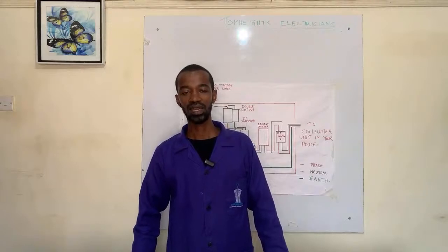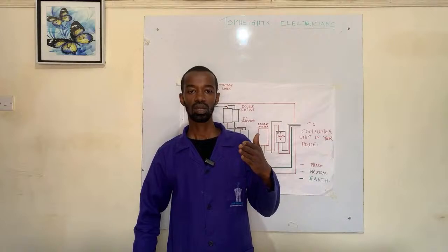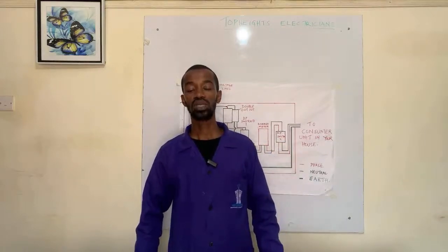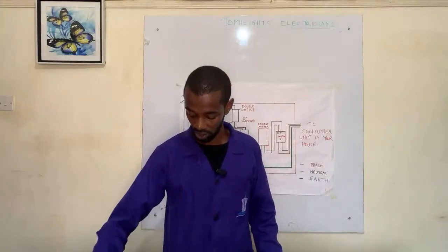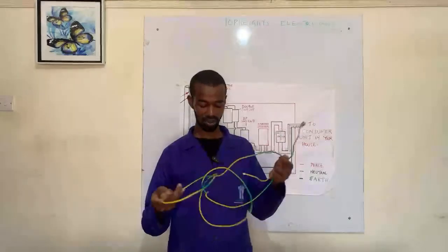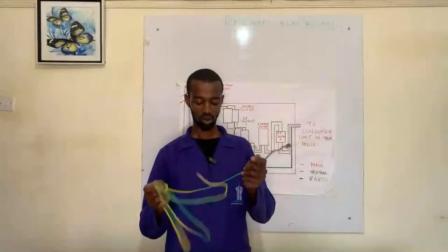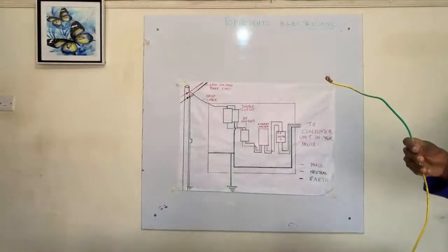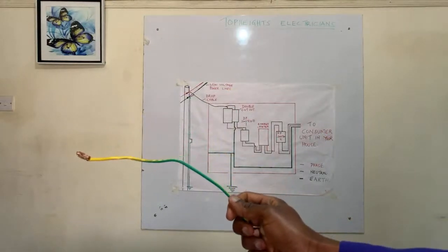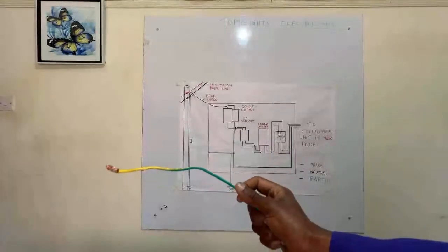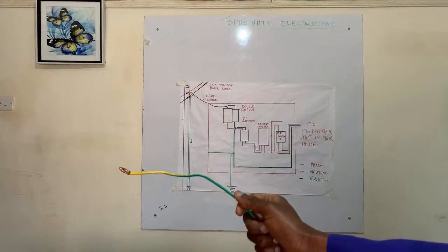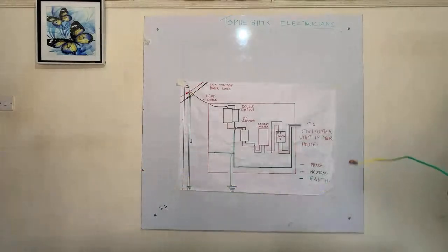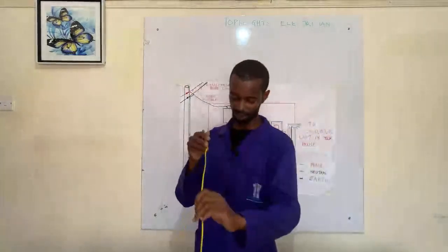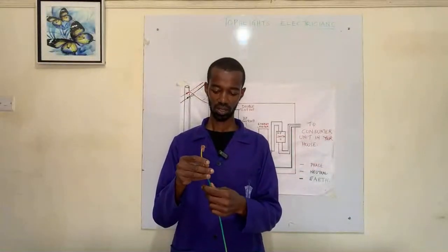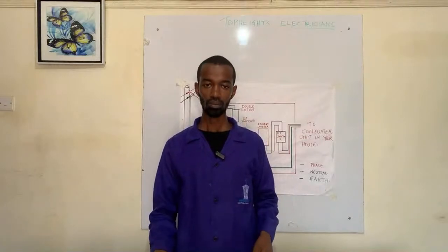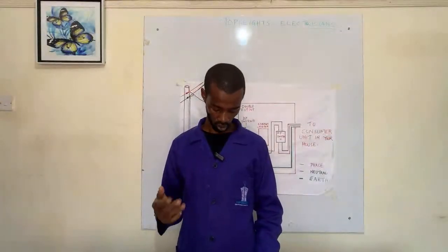An electrical leakage or charge leakage on electrical appliances can also damage those appliances. That is why it's important to ensure your earthing connection - represented by this wire, normally yellow with green stripes or green with yellow stripes - is present for every circuit. Someone asked me whether there should be an earthing connection on the lighting system, and yes, it is very important to have earthing on each and every circuit. This protects your appliances as well as anyone using the electrical installation in that house or establishment.